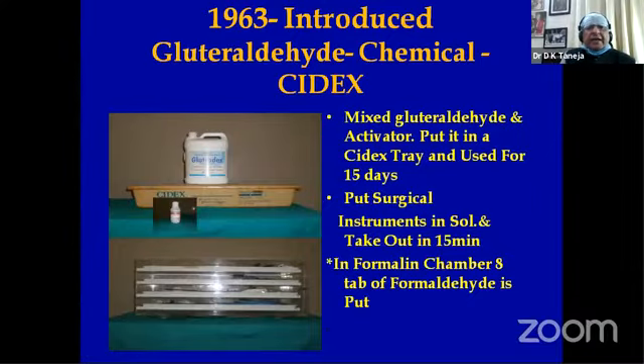The other thing is what we call a formalin chamber. So you have about 8 tablets of formalin, which are put inside this chamber. You can put the rubber instruments, the other sharp instruments, or any other instrument that you want to sterilize. Leave it for about 8 hours, and then you can remove it because it has a very pungent smell. The one thing that we do not know, and which I want to emphasize, is that formalin is carcinogenic.